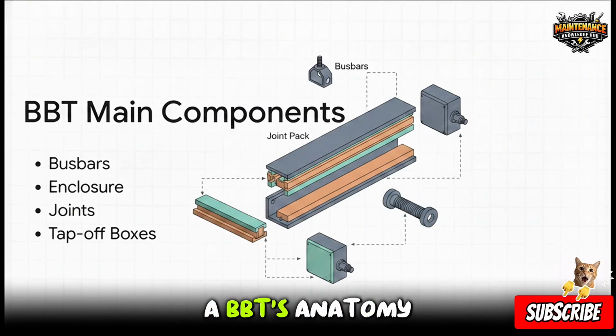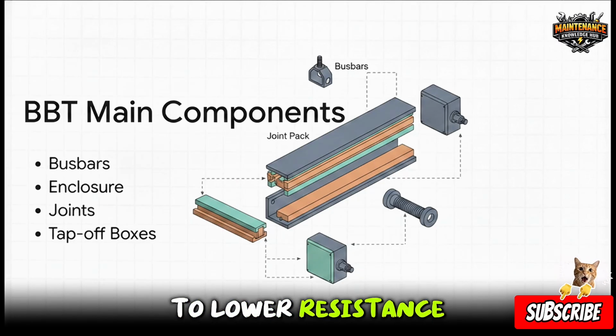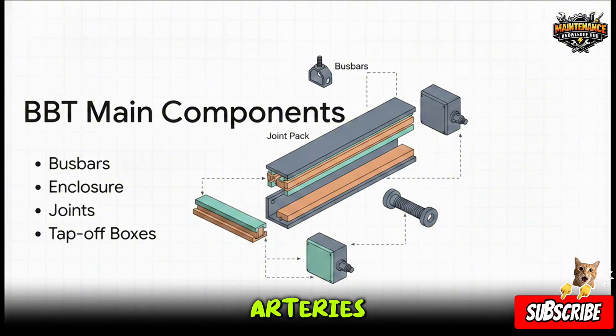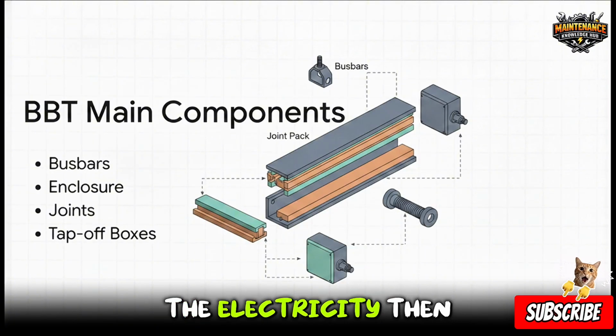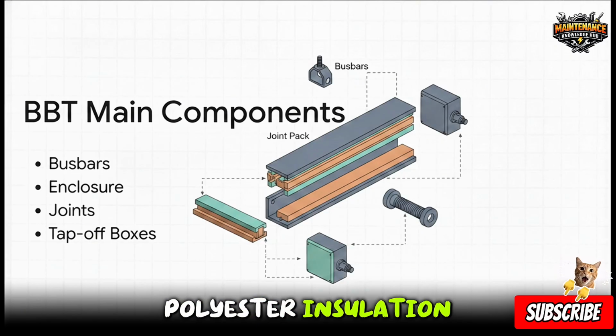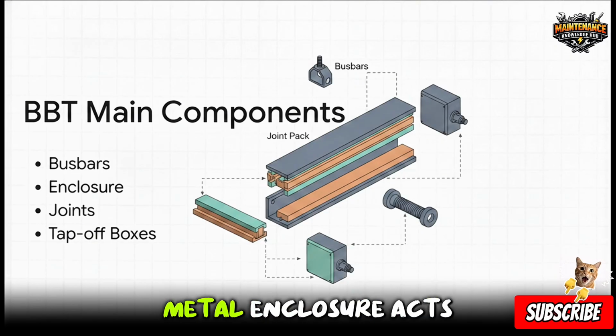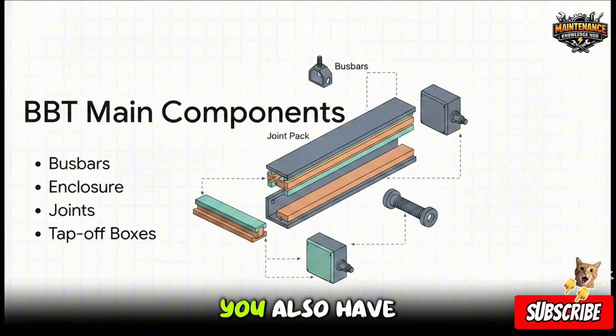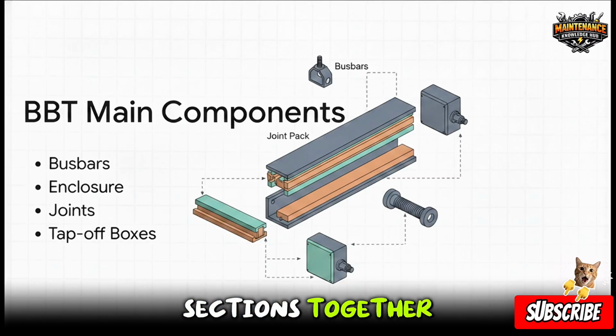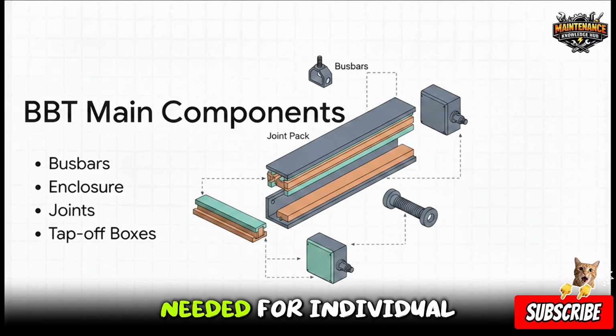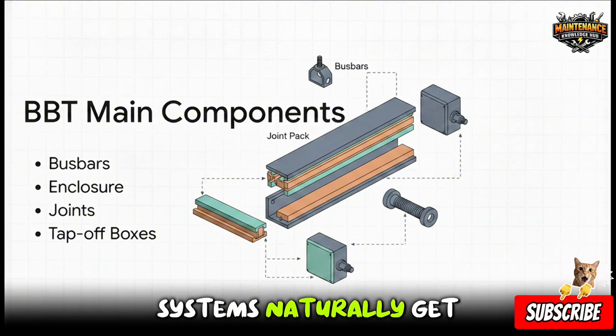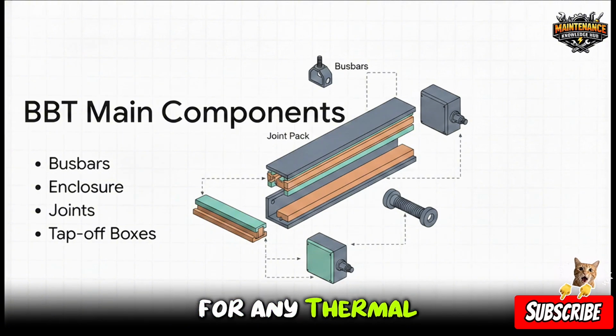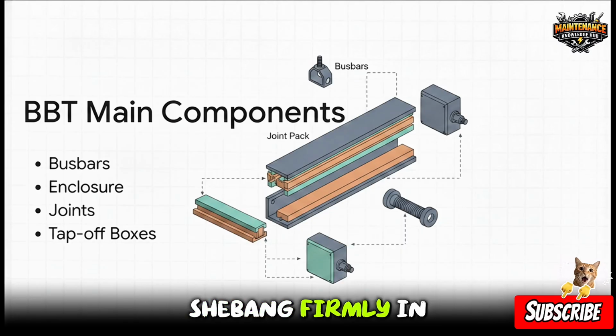You can kind of think of a BBT's anatomy like a living organism. You've got the copper or aluminum bus bars, which, by the way, are usually tin or silver plated to lower resistance, and these act as the main arteries carrying the lifeblood of the building, the electricity. Then the epoxy or polyester insulation keeps that energy safely contained, while the earthed metal enclosure acts as a protective skeleton. You also have joint packs connecting the modular sections together and tap-off boxes. Those act a lot like capillaries, safely diverting the power exactly where it's needed for individual loads. And since these systems naturally get warm, expansion joints compensate for any thermal changes, while the supports and hangers hold the whole shebang firmly in place.